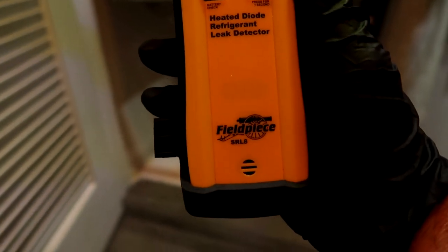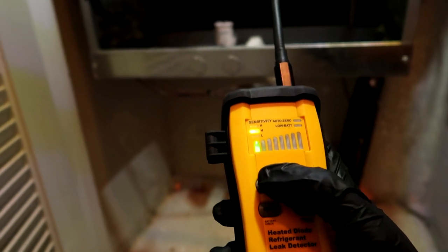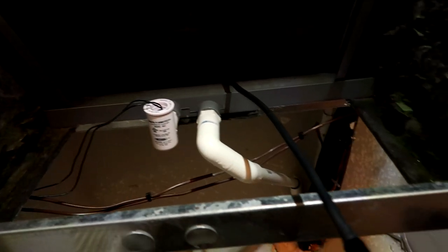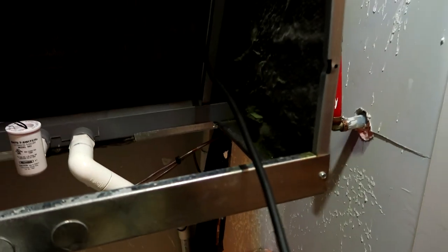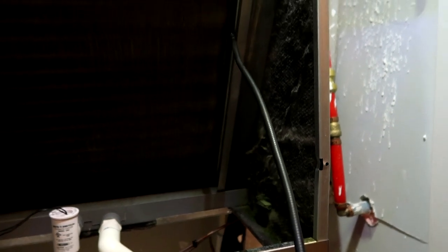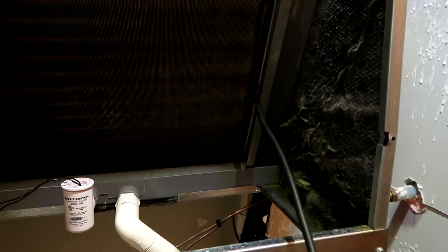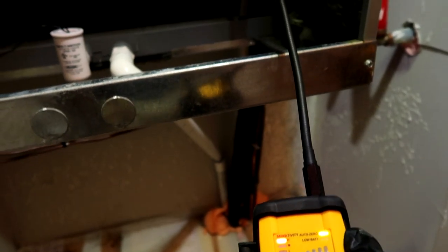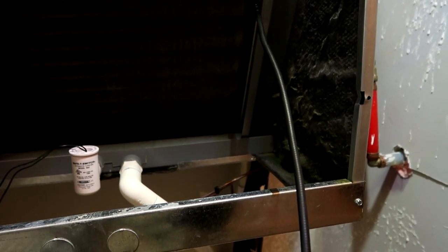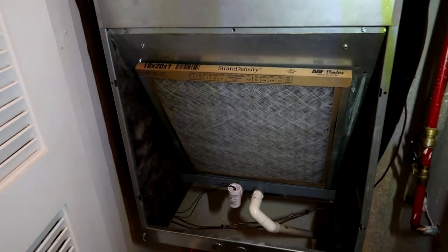Got the old Fieldpiece SRL8 leak detector - always leave tool links in the description below if you want to get one. I'll go with medium sensitivity first. As you guys know I have 200 leaking coils - they are all leaking. Oh, there we go, right up in there - it was right along here. Let me go to high sensitivity. There it is - it's another leaker. They are all leaking. We'll add it to the list.